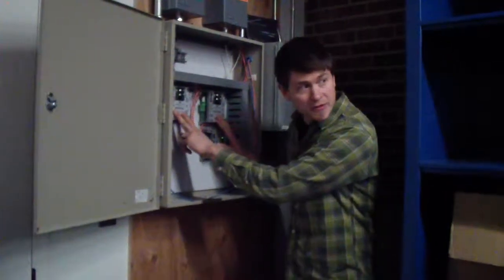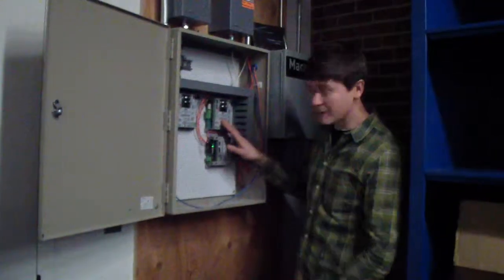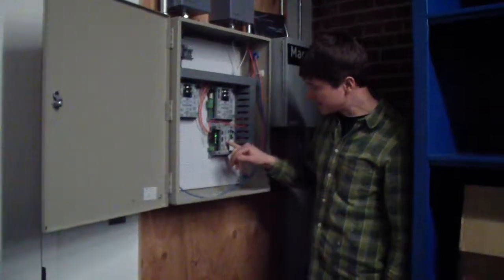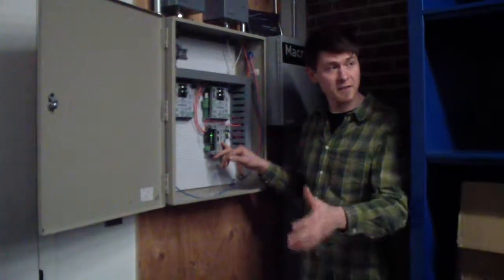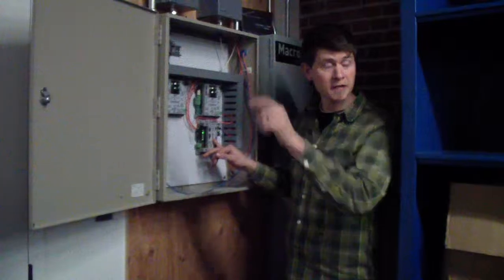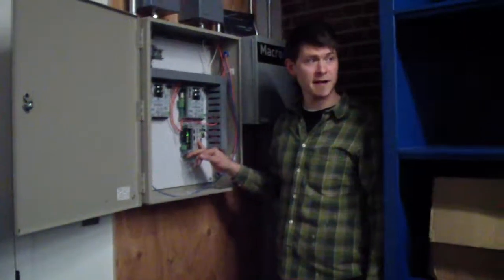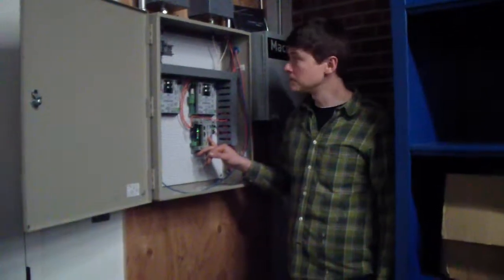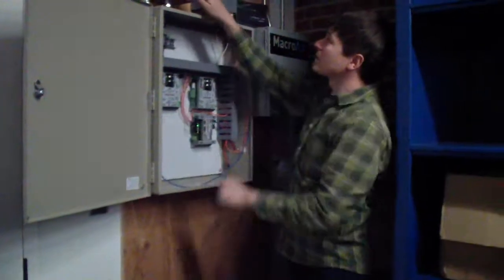So this would be the upper thermostat, feeds in here. This would be your lower thermostat, and then this is for your communication. So this is actually the BACnet communication to the fans themselves through the 3 Yaskawa drives. Okay. These are the power supplies for both.